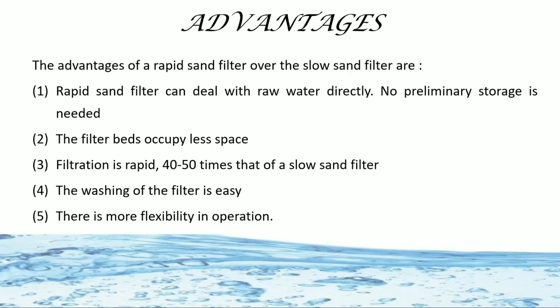Then, advantages of rapid sand filter. Rapid sand filter can deal with raw water directly. There is no need of storage. The filter beds occupy less space. Filtration is rapid, 40 to 50 times that of slow sand filter. The washing of the filter is easy. There is more flexibility in operation.